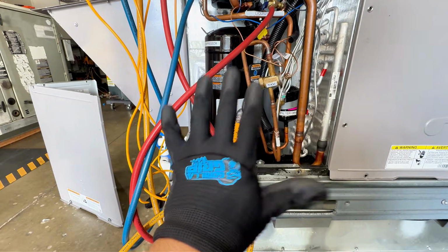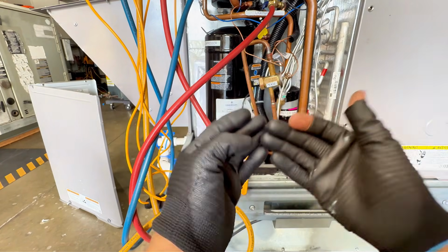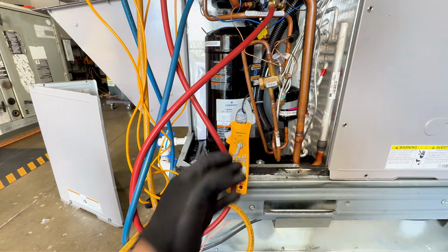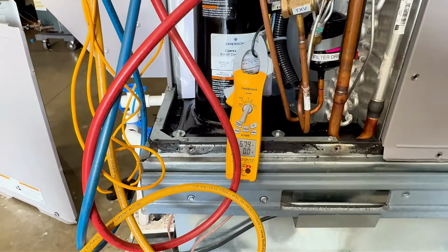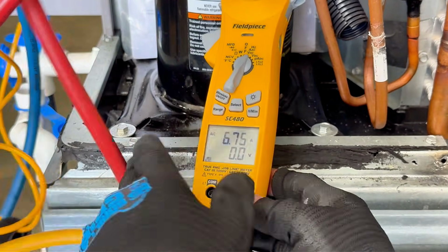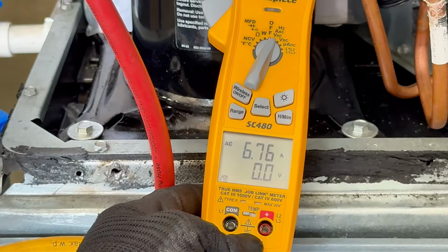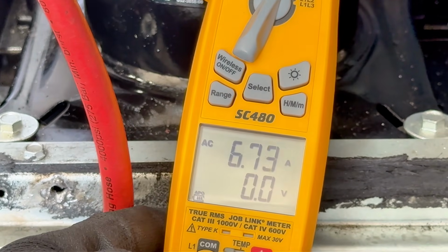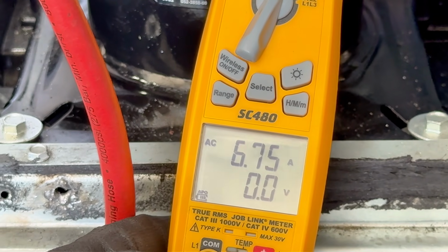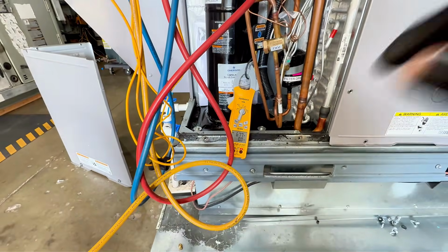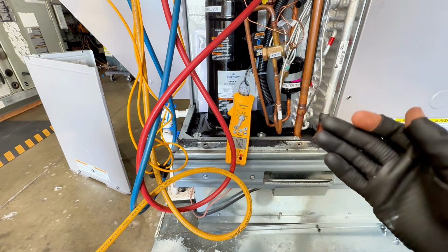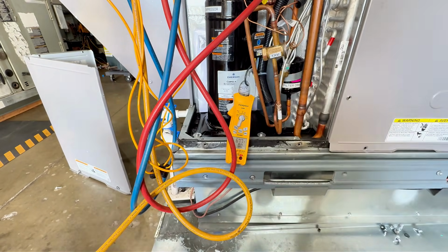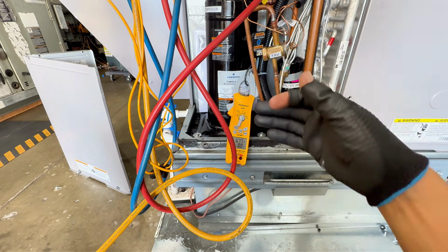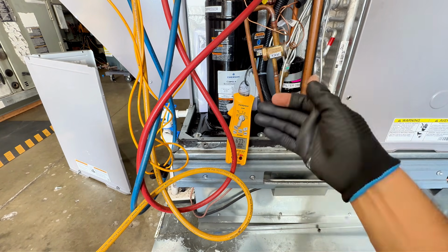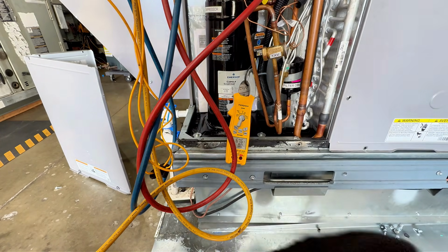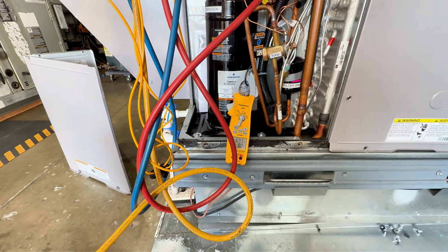Okay, and the fifth question we're going to answer is, how do the compressor's amps go up? So you are going to have amps, obviously, because it's on and needs a lot of current to work. And right now we're pulling, if you see, 6.7, almost 6.8. But we're going to go over two specific ways that your amps would go up. And it's just good to be mindful of it and keep an eye on it. So we said 6.8. So amps would go up if you have a dirty condenser.